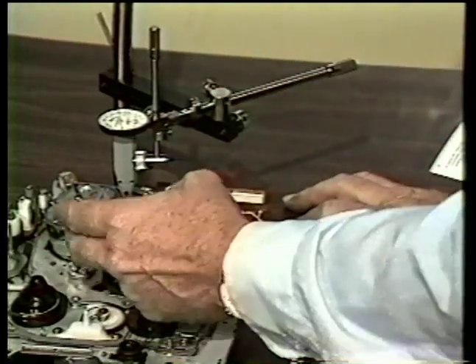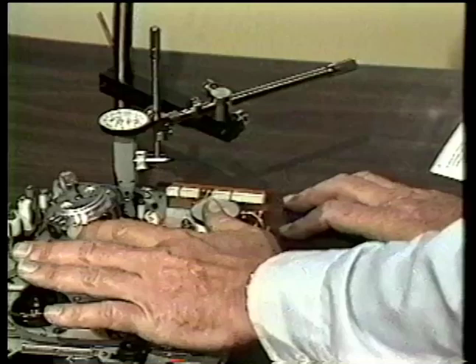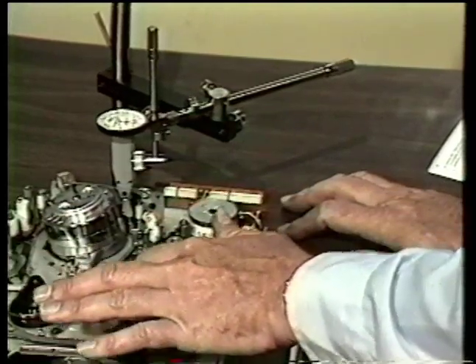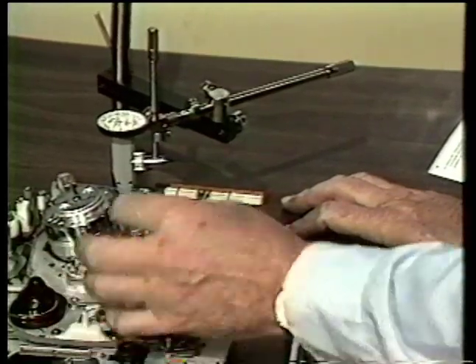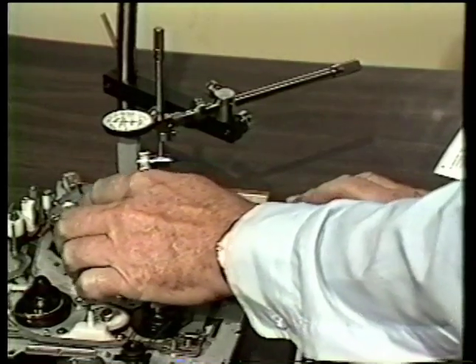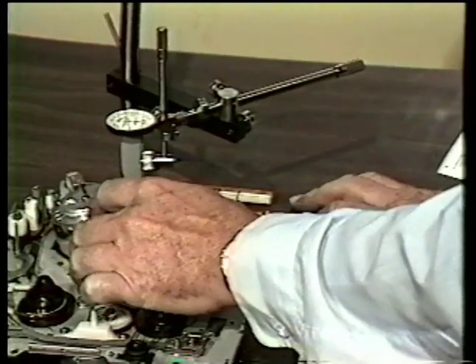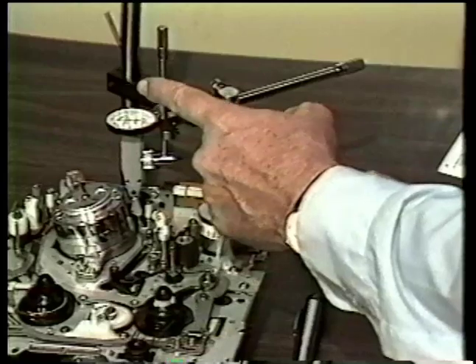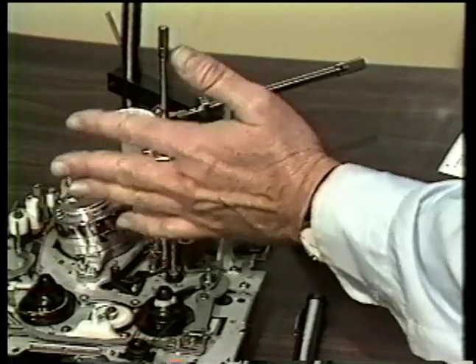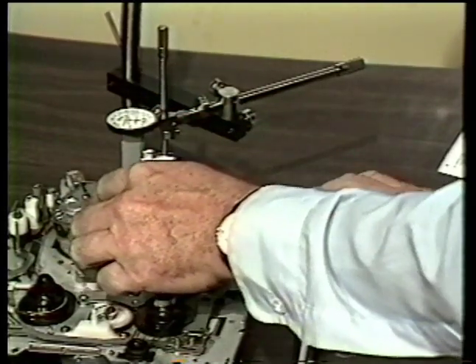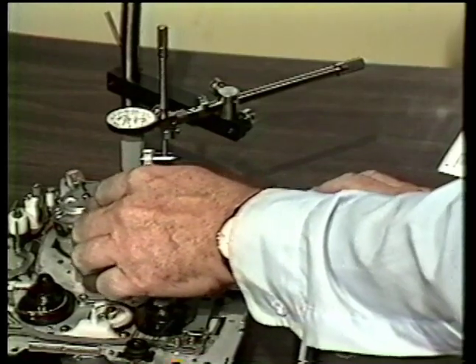So once we're set up, don't lean on the machine because the metal will flex enough that that will change things, but just rotate the head tip through and subtract the base dimension, the starting dimension, somewhere in the preload zone. It could be anywhere from 0 to 30 or so microns. We'll subtract that number from the upper number.